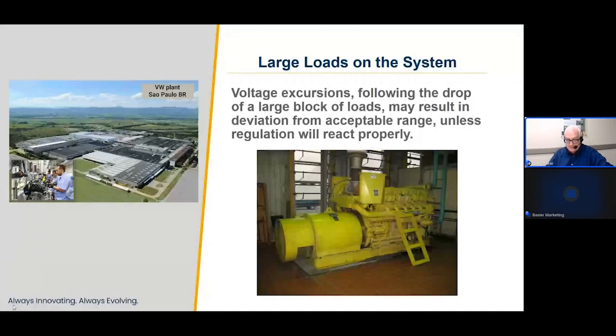Within 10 kilometers of the supermarket is a rather large Volkswagen assembly plant in the nearby city of San Bernardo do Campo. The Volkswagen plant would shut down every Saturday at 5:00. When that plant shut down, they shut down all the machines and really dropped quite a bit of load off the line. My teammate learned that the same transmission line feeds the power to our client's supermarket and the Volkswagen plant. At the time that the Volkswagen loads were all shut down, what caused the power to go off for my supermarket was that an overvoltage relay tripped the circuit breaker feeding the supermarket.